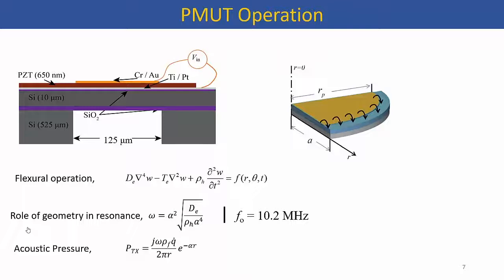A typical PMUT works by having a stack of layers — you require at least two: one passive material that doesn't do much, and one piezoelectric material. You apply voltage across the piezoelectric material, which causes generation of in-plane stresses. These in-plane stresses lead to a bending moment, and that bending moment causes flexural mode of vibration in the membrane. This vibration is maximum when the bending moment location is at the point of maximum slope in the vibration mode, which happens to be around 65 to 70% of the total membrane.